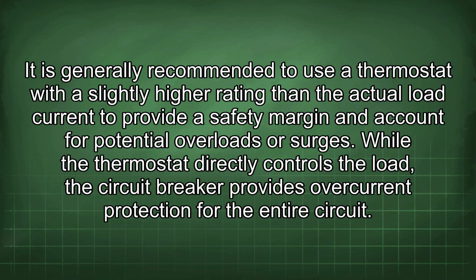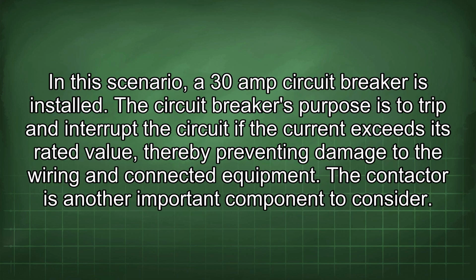While the thermostat directly controls the load, the circuit breaker provides overcurrent protection for the entire circuit. In this scenario, a 30 amp circuit breaker is installed. The circuit breaker's purpose is to trip and interrupt the circuit if the current exceeds its rated value, thereby preventing damage to the wiring and connected equipment.